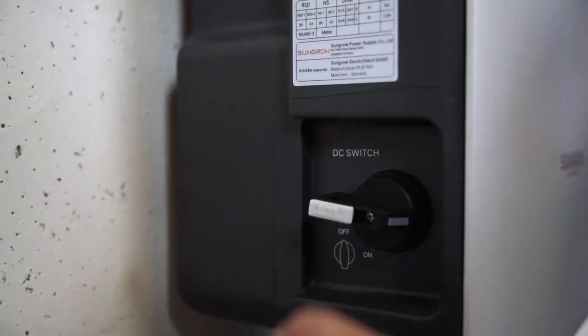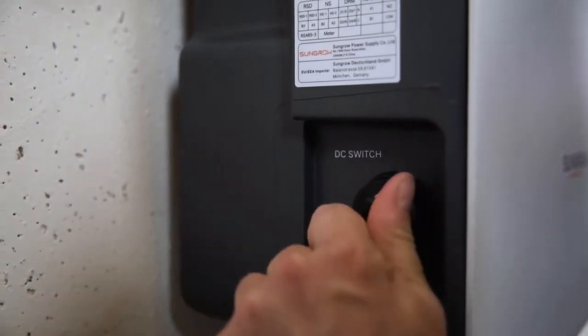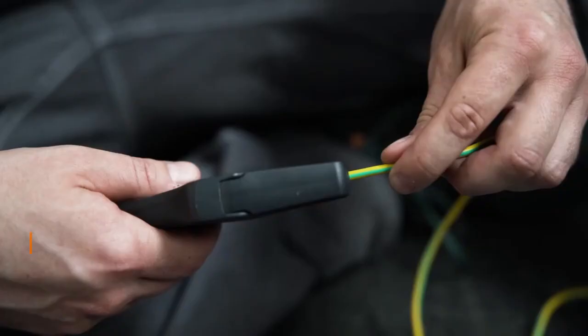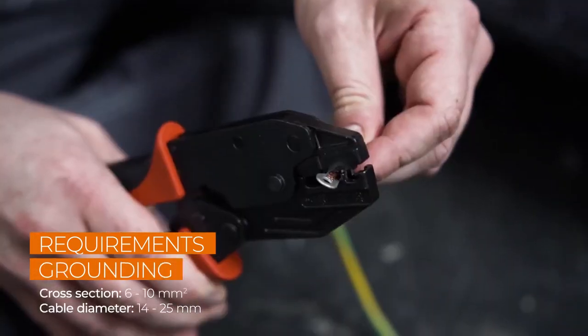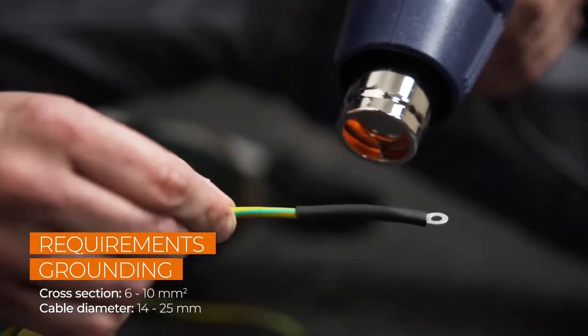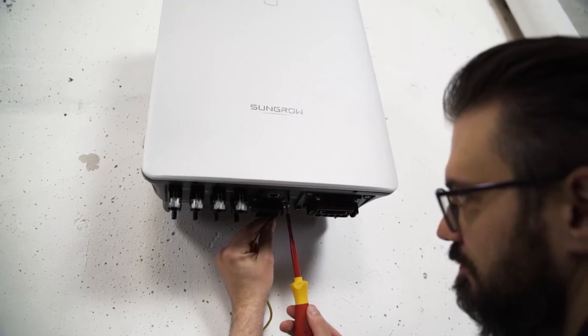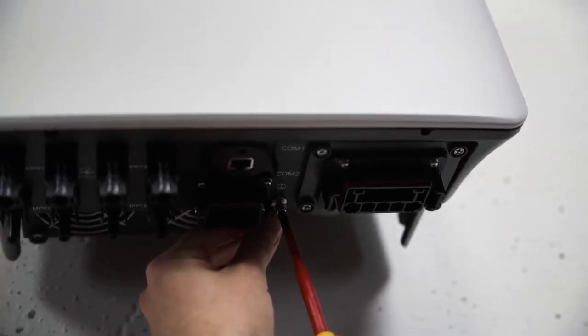Furthermore, you have to set the DC switch on the left side of the inverter from ON to OFF. Now let's connect the inverter to ground. There is a grounding terminal at the bottom of the inverter. Connect it to the general grounding of the house.